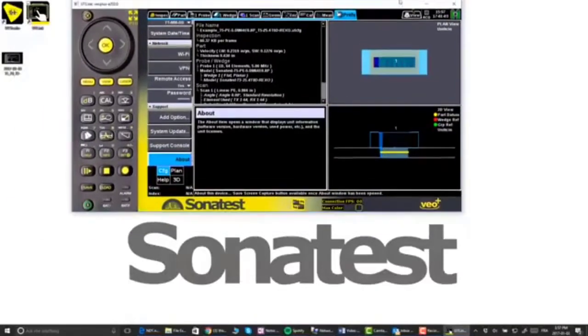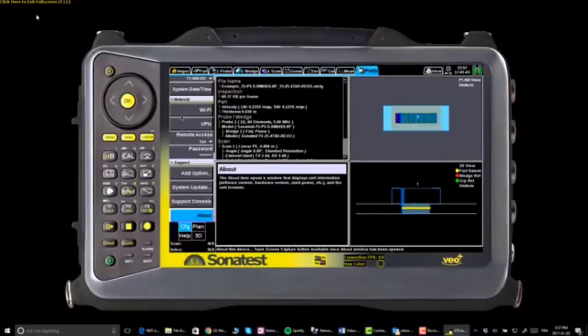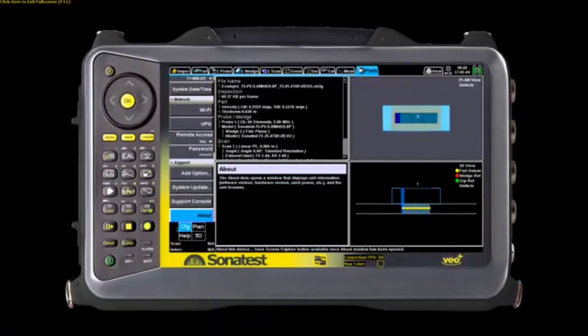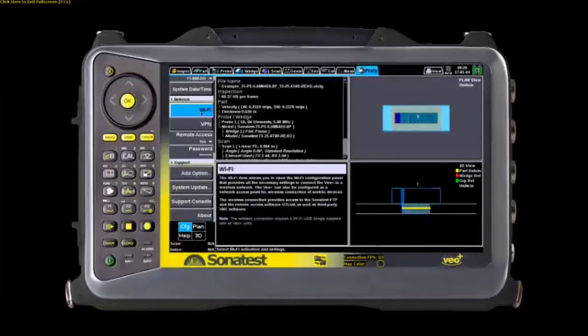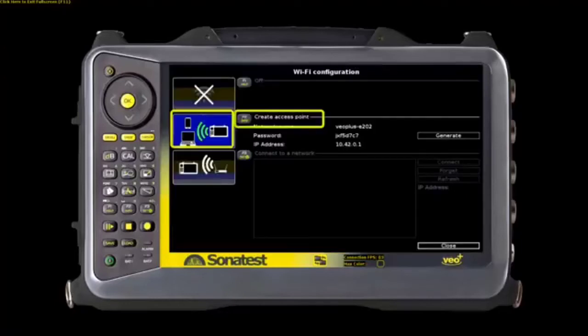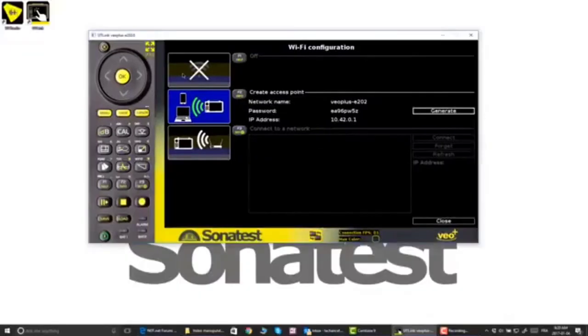The second way of connecting our device is to create a hotspot using the Wi-Fi dongle which is supplied with the VEO Plus. To generate a hotspot, we have to go back into the Wi-Fi configuration page. We need to select Create an Access Point. We can now see the name of the generated network, the password and the associated IP address. Every time we press Generate, a new password is issued to the network. We can now connect the computer to the generated hotspot.